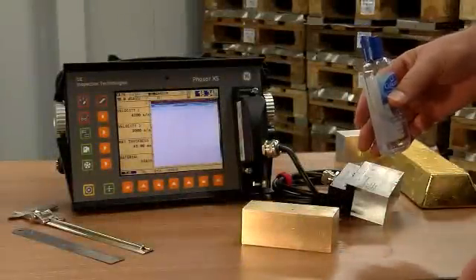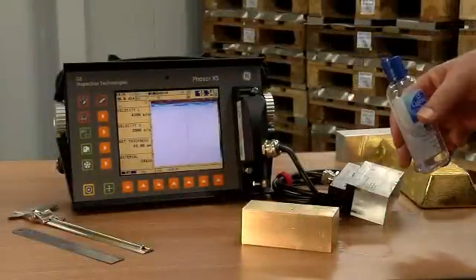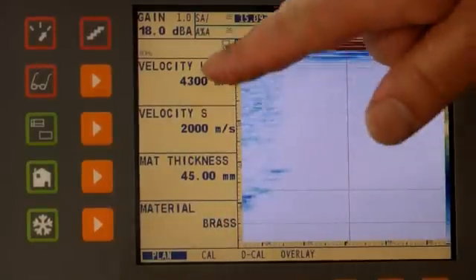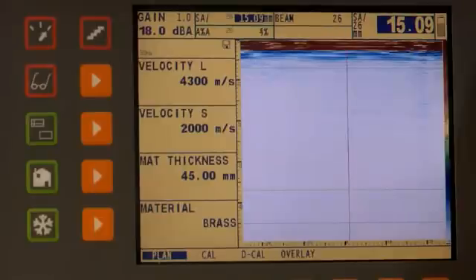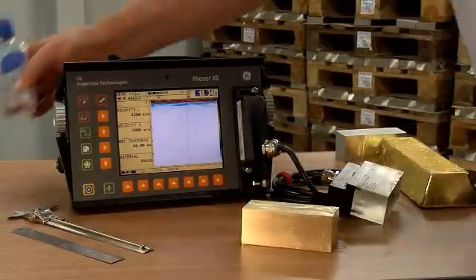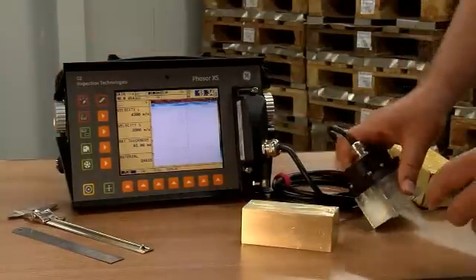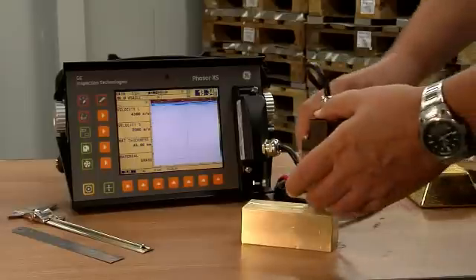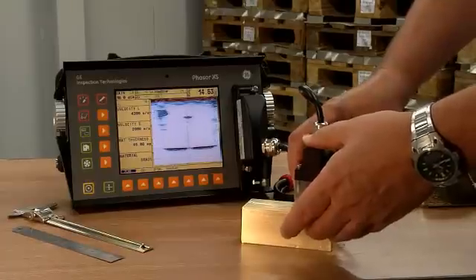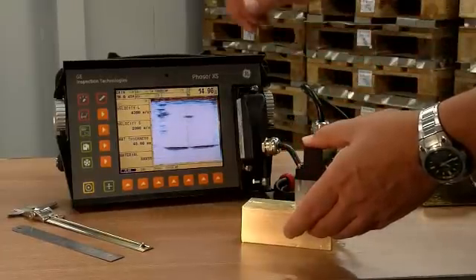We're now going to test a brass sample with the Phasor XS. First thing we have to do is select a different material for the instrument, which has changed the acoustic velocity. We then need to put the couplant on in exactly the same way that we did with the gold bar.